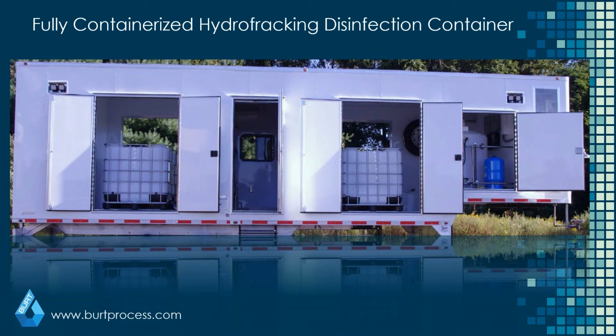And there are some differences with these. Obviously, these are built onto a unit which can actually be moved by a vehicle. Often all the tanks in them have to be DOT rated, and you do have to have, obviously, a non-hardwired power supply to these, whether that be a generator-based system, if it's a more remote site, or more of just a plug-in system, specifically for 460 volt or 120 volt, whatever the actual power requirements are for these systems.